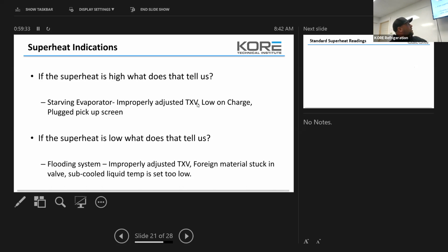If the superheat is low, what does that tell us? If the superheat's too low, it's going to flood the system. The one thing I will tell you is, depending on the manufacturer and the type of evaporator you're dealing with, you can look pretty much anything up on Google.